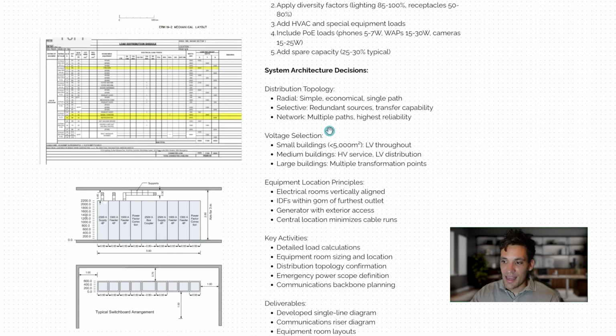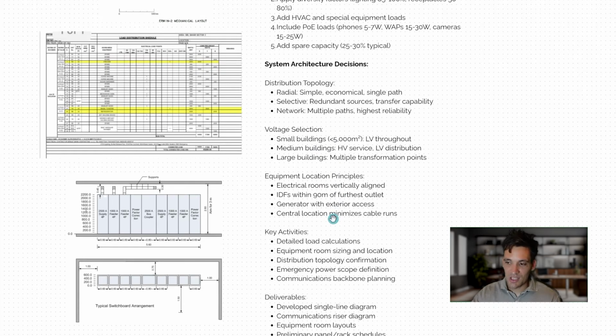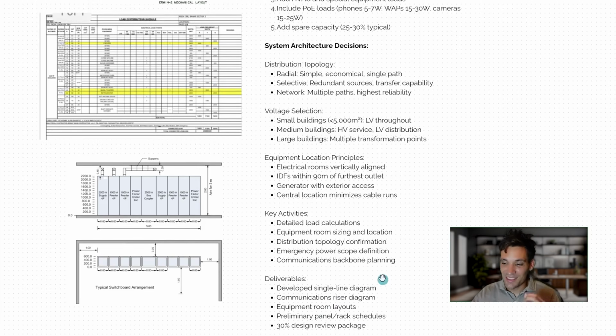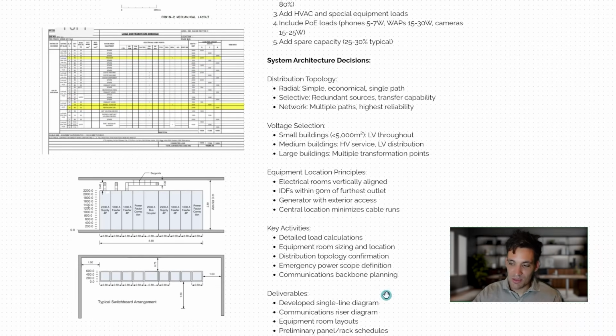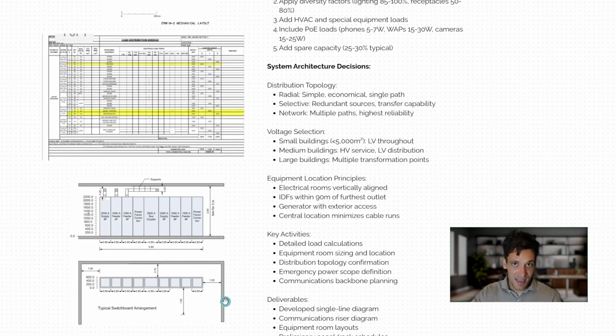And we'll finalize our system architecture: the distribution topology, the voltage selection, what voltages we're going to use, the equipment location, where the equipment rooms are going to be, where the communication room is going to be. Are we going to have a generator with exterior access? Key activities will be detailed load calculations, sizing the equipment rooms, the emergency power scope and definition, how it's going to connect, and we'll get our detailed single line diagrams, maybe communication diagrams, equipment room layouts, maybe very high-level preliminary distribution board drawings, and again, another design package we're going to send to the client to review in detail.